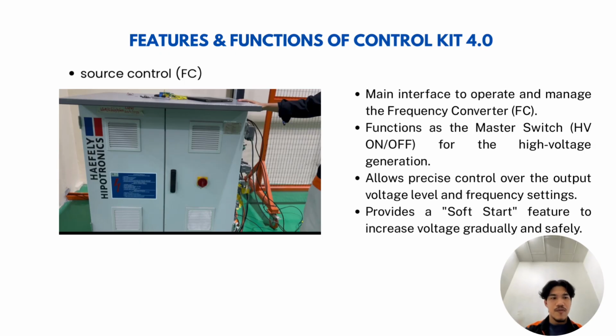I will talk about the configuration, the procedure of setting the kit control and picoscope. The first slide is the features and functions of control kit 4.0. This is the source control, which is a frequency converter. Its function is the main interface to operate and manage the frequency converter. Next, it functions as the master switch for high voltage on or off for the high voltage generation. Also, it gives precise control over the output voltage level and frequency setting. It provides a soft starter feature to increase voltage gradually and safely.